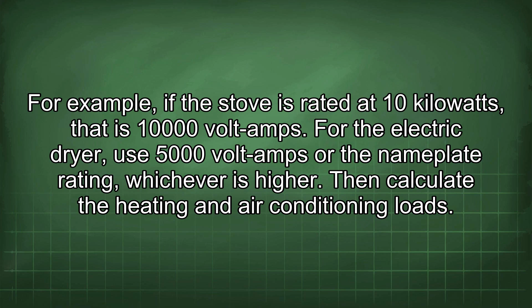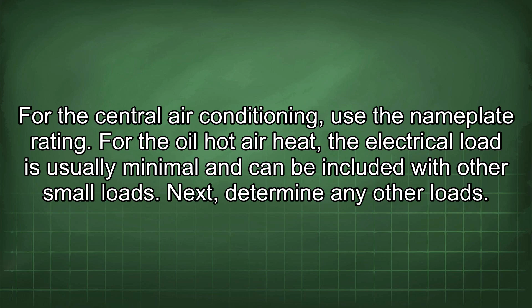For the central air conditioning, use the nameplate rating. For the oil hot air heat, the electrical load is usually minimal and can be included with other small loads. Next, determine any other loads. Include any other significant electrical loads, such as a partially finished basement. Then apply the demand factors.